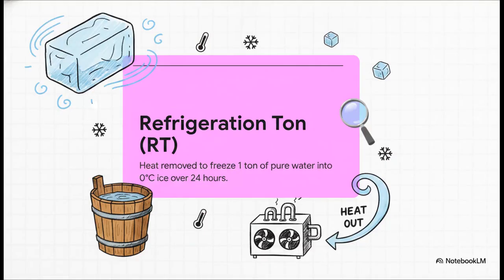Let's start with the refrigeration ton, or RT for short. This is all about the exact amount of heat removed from an indoor space. And the history here is actually pretty cool. Back before modern AC, people literally used massive blocks of ice to keep things cold. So 1 RT was defined as the exact mathematical amount of heat you have to suck out of 1 ton of pure water to freeze it solid in exactly 24 hours. When you buy a 100 RT machine, you're buying the power to freeze 100 tons of water a day. Simple enough, right? It's entirely focused on the heat pulled from the room, nothing more.